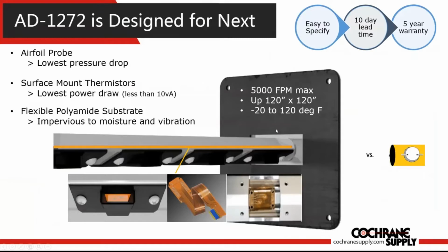So here's kind of the difference in construction at a probe level. So we have, again, the airfoil probe. And the advantage over a tube is the pressure drop for the air going across that probe. Much, much lower, much more efficient. And we use surface mount thermistors. We have very low power draw, less than 10 VA. And all of these thermistors are housed inside a flexible polyamide substrate. And this is completely impervious to moisture and vibration. There's no point-to-point wiring here. It's kind of like, once again, comparing radial tires to bias ply tires. This is new technology, and this old technology here, it works, nothing wrong with it, but it's definitely not the latest technology.